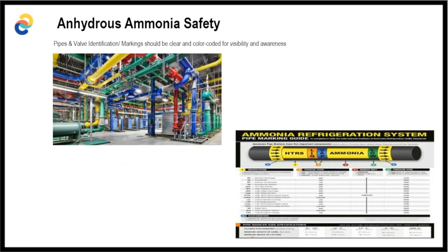Okay, pipe marking. Pipe marking should be installed for accurate identification of flow. This is also to distinguish the type of medium present in the pipe as well as its characteristics: the physical state, liquid or gas; the relative pressure, whether it is high pressure or low pressure; the pipe service, for example, if it's the hot gas line, suction line or condensate line; and also the directional flow.